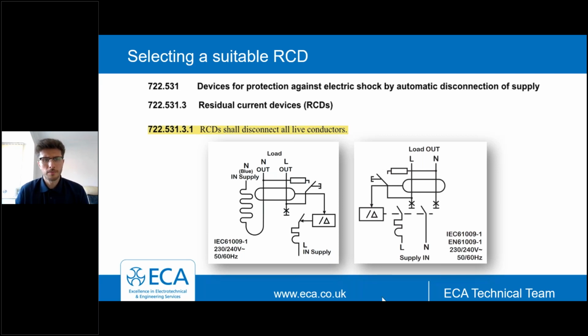Now, the image to the right shows a single pole and switched neutral device. So in the event of a fault happening here, both line and neutral conductors would disconnect. So we call it a single pole and switched neutral because the overcurrent protection is in the line conductor, and that is signified by the curve symbol here for protection against overload, and then the protection against short circuit shown here. So it's important when we select these devices that we're ensuring they are suitable to disconnect all live conductors.